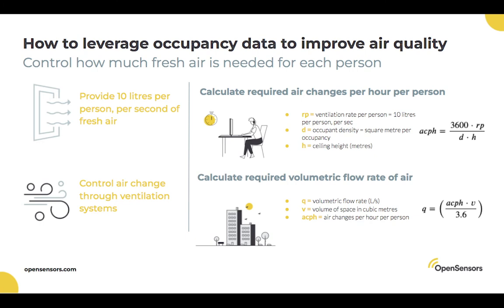And they then were able to go to their building manager and say, even when our occupancy is at like 60%, our CO2 levels are 1,000 plus. This is not hitting any standards that we want to be, nor is it hitting things like the WELL Building Standard. So it gives you the information to go and challenge people to make the change that you need to be seeing, even if there's something that you're not directly in control of.